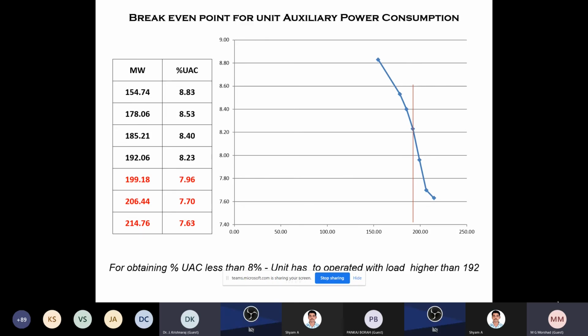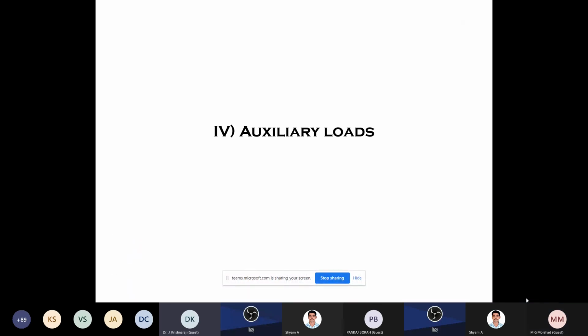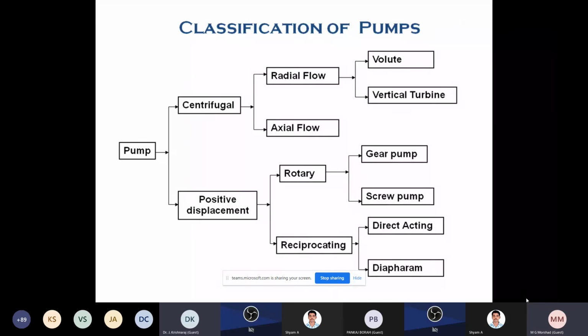Normally that is the case, but nowadays, because of the technical minimum, we are maintaining the load at 140, 130, like this, 150 also. So automatically, auxiliary power consumption is also increasing. Our net heat rate is also getting increased because of this technical minimum. So this is my observation about the technical minimum. Now, I am coming to the auxiliary loads. Some few pages are there. Within 10 minutes, I'll finish it up.